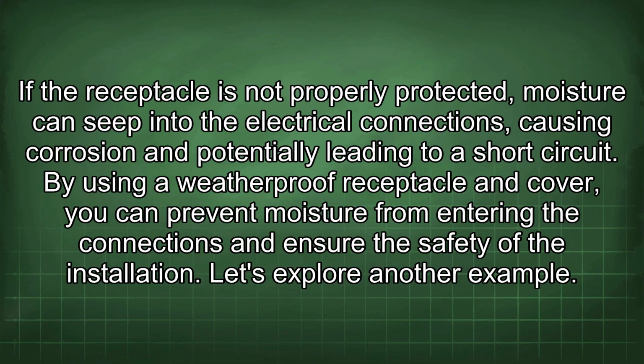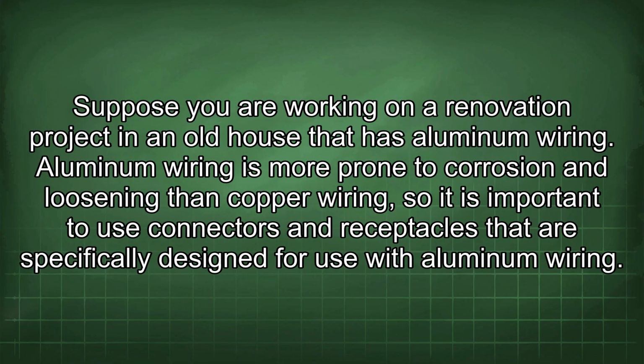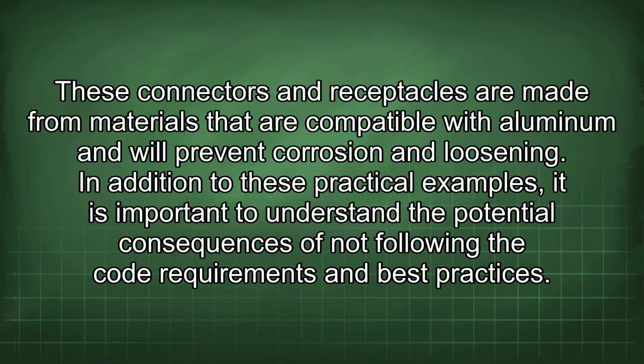Let's explore another example. Suppose you are working on a renovation project in an old house that has aluminum wiring. Aluminum wiring is more prone to corrosion and loosening than copper wiring, so it is important to use connectors and receptacles that are specifically designed for use with aluminum wiring. These connectors and receptacles are made from materials that are compatible with aluminum and will prevent corrosion and loosening.